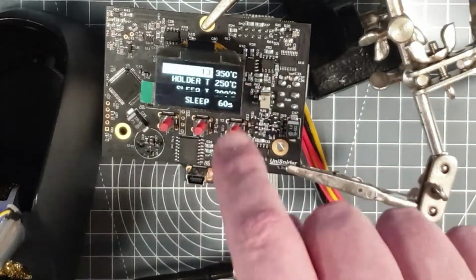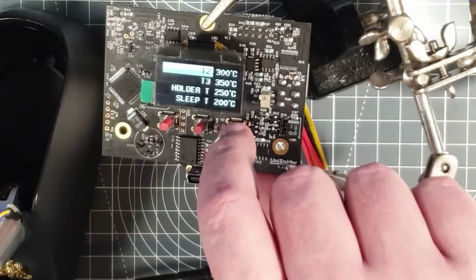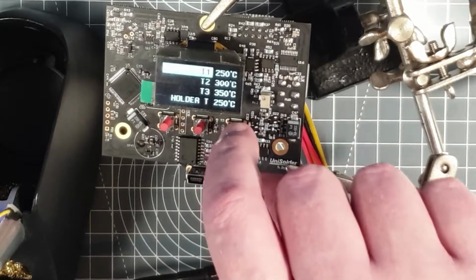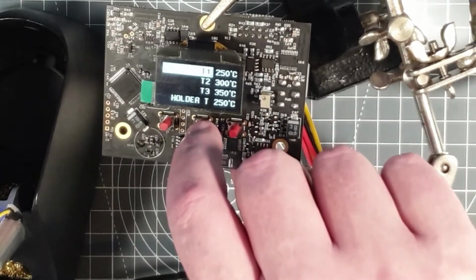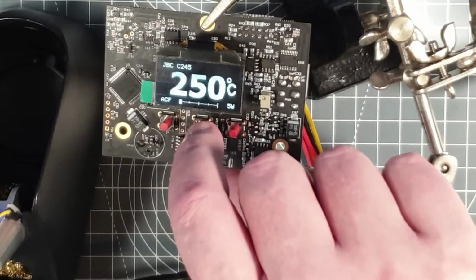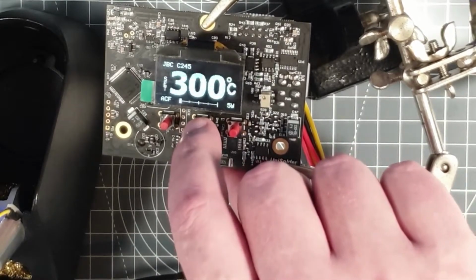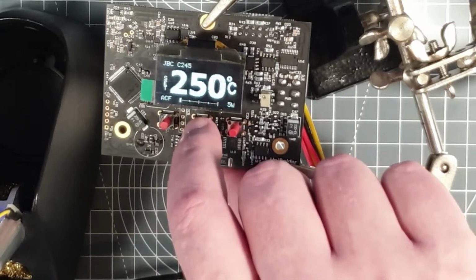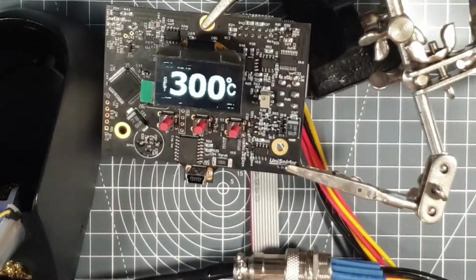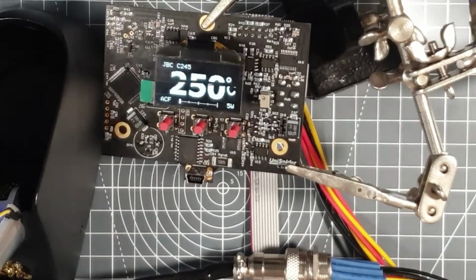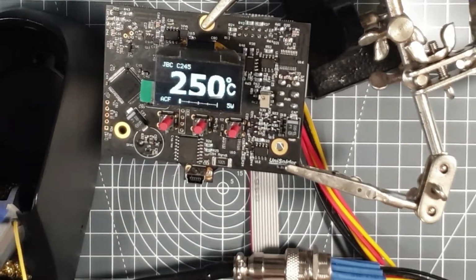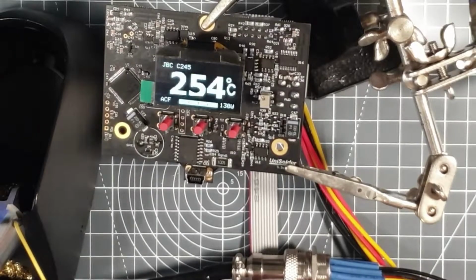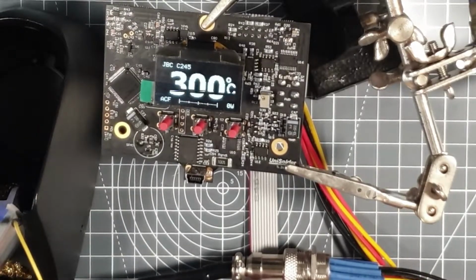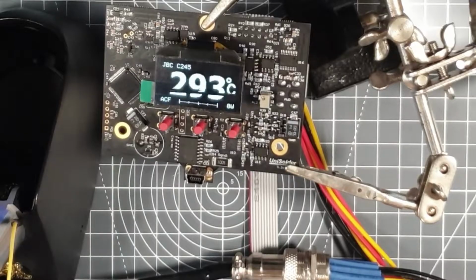And then we have the actual temperatures set: 350, 300 and 250, and you can press the middle button to get to those temperatures. Those are set temperatures. So if I do that, that's set to 300. I can do 350 or I can do 250. I had it set to 300. It's at 250. If I remove it from the holder, it'll immediately start going up in temperature. As I put it back in the holder, the temperature will start dropping, and then after 60 seconds it will go to 200 degrees.